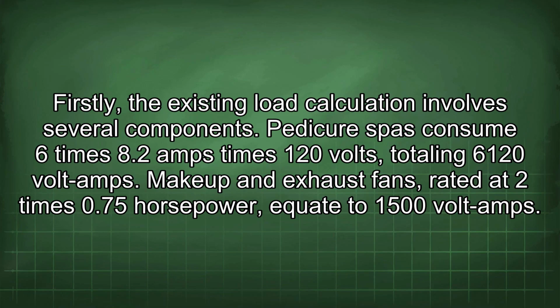Firstly, the existing load calculation involves several components. Pedicure spas consume 6 times 8.2 amps times 120 volts, totaling 6,120 volt amps. Makeup and exhaust fans, rated at 2 times 0.75 horsepower, equate to 1,500 volt amps.